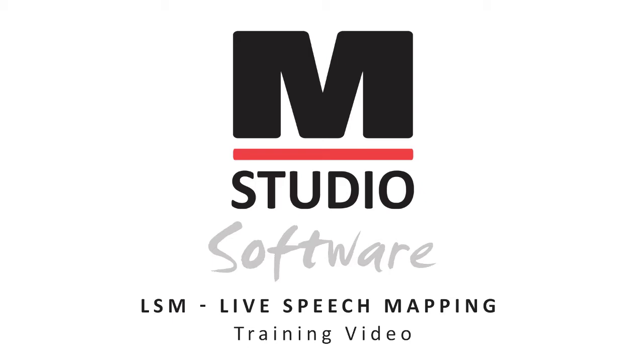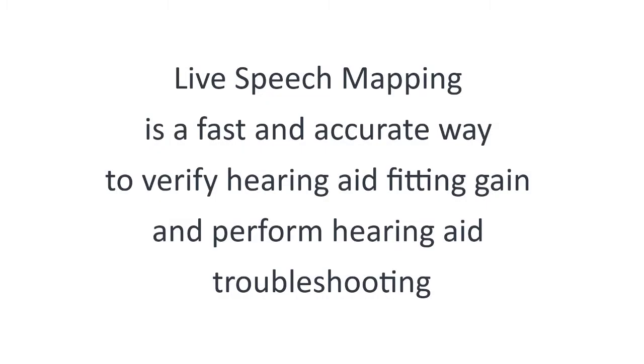In this video we will review live speech mapping and how to perform live speech mapping measurements within the M Studio software. Live speech mapping is a fast and accurate way to verify hearing aid fitting gain and perform hearing aid troubleshooting.